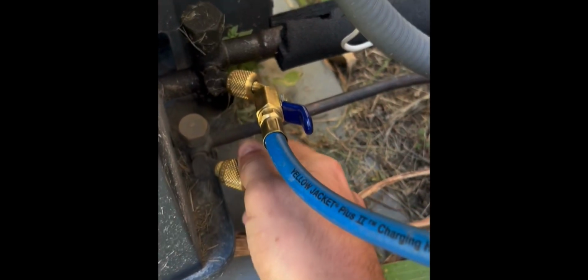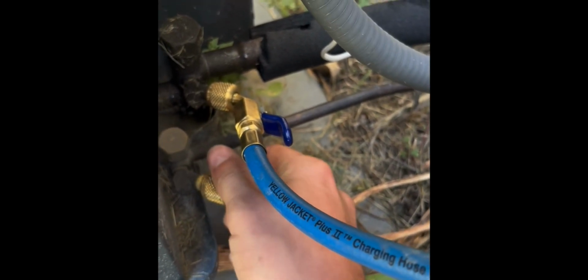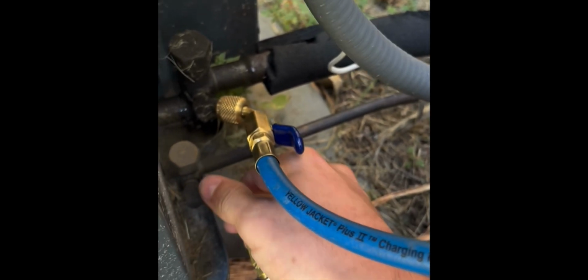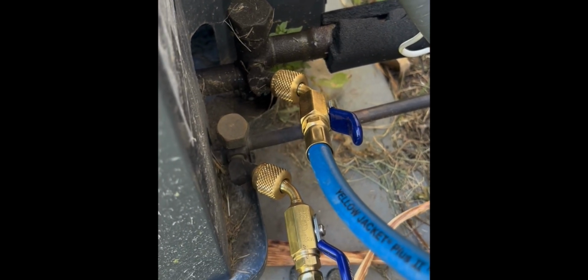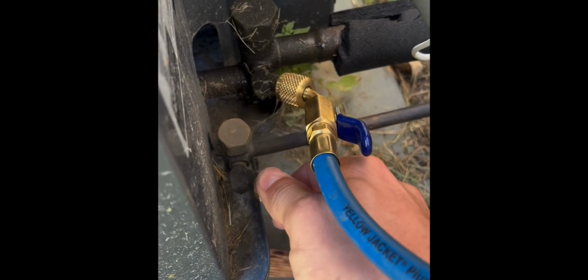Now make sure on this one you really want to be quick when you put it on there, because you could get some refrigerant discharge shooting out, like that. Now when you look at these, you want to make sure there's no frost building up on either the brass pieces here or the service valves down here, because that means you got a leak, or you don't have it on there all the way, or you got a bad O-ring or seal inside your hose there.